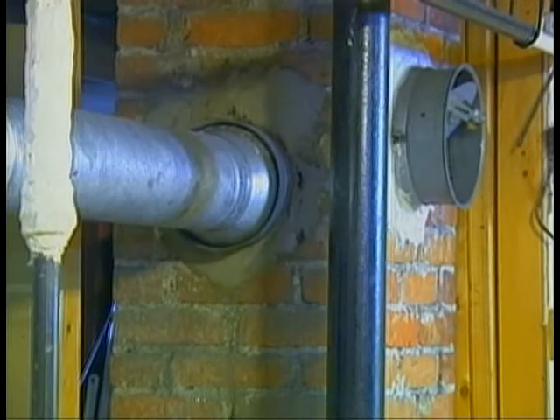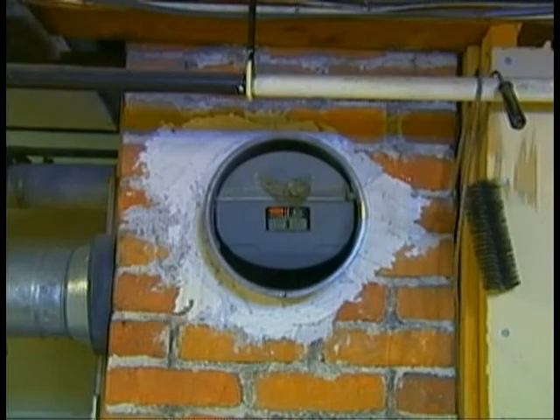The connection of the metal exhaust vent to the chimney should be examined for soot and creosote stains, exhaust fumes, a loose fit, and corrosion. The inside should be checked for blockage and corrosion. The chimney furnace damper should be inspected for free movement, corrosion, backdrafts, staining, and soot or creosote blockage.